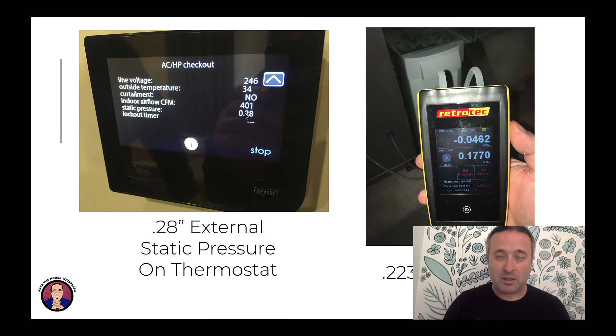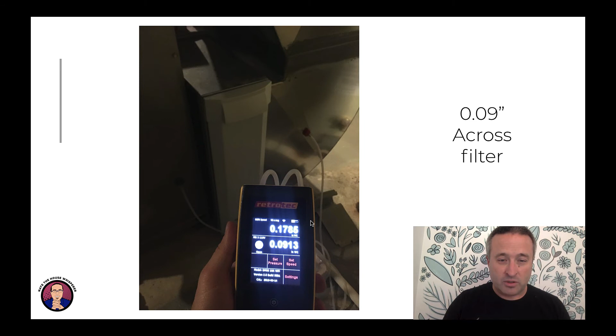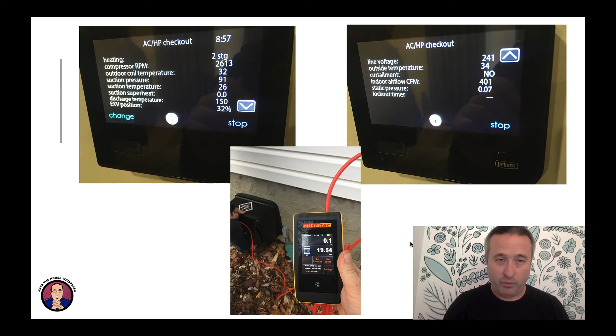Here is static across the filter, so you can see there's one of my probes before the filter and then the other probe after. 0.09, which is a little more than I would like. Not awful, but a little more than I'd like. And then I turned it down to 2-stage to see what happened to the static. So let's see, where does it show? Indoor airflow is 400 CFM, and we're down to 0.07 static, and that led to about 20 CFM of fresh air coming in. So whenever this fan is running on low, he's at least getting 20 CFM of fresh air, which is very important for a whole bunch of things. We were doing this before it was cool.